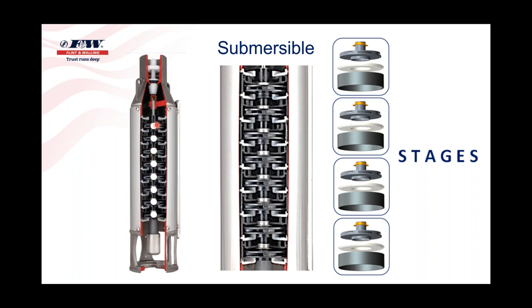And Flint Walling has never, ever destaged their submersible pumps, where I know that has been a practice within the pump industry, where they've taken cost out and they'll take impellers out and they'll tighten the tolerances down on everything else that's left. But you've got a pump that costs a little less, but it easily sand locks, and anything else that gets in there, because the tolerances are so tight.